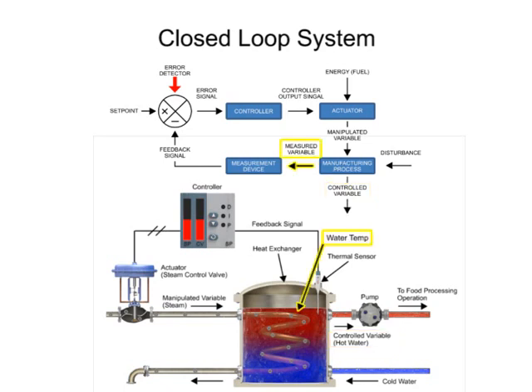Measured variable monitors the status of the controlled variable. Water temperature is the measured variable in the process. The measurement device senses the measured variable and produces an output signal that represents the status of the controlled variable. The thermal sensor that measures the water temperature in the heat exchanger is the measurement device.